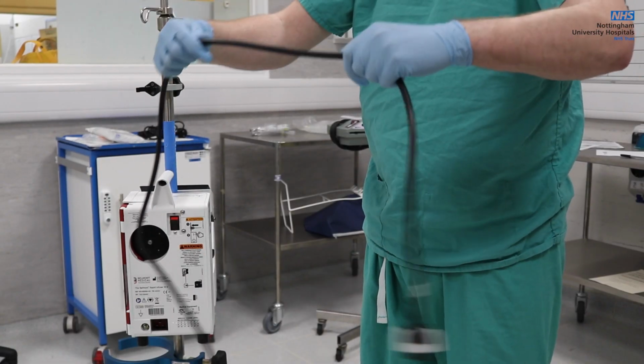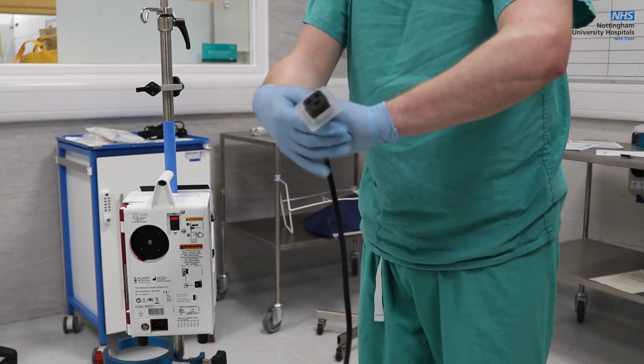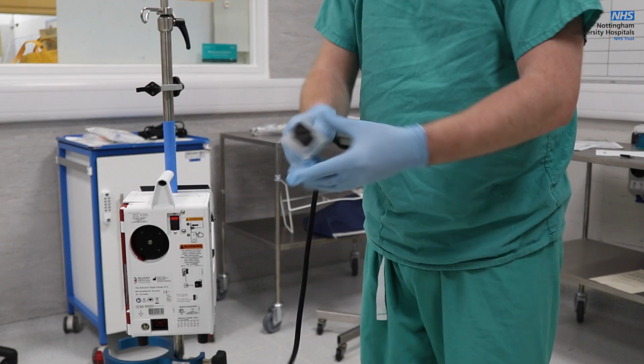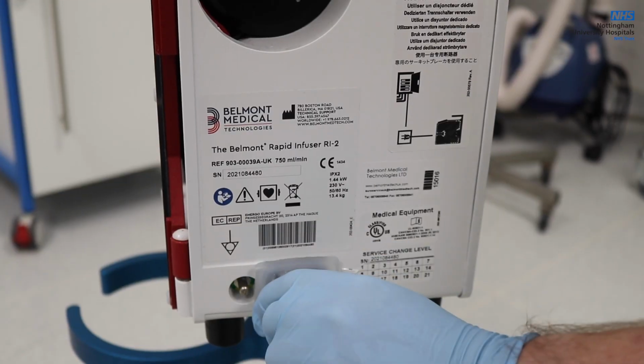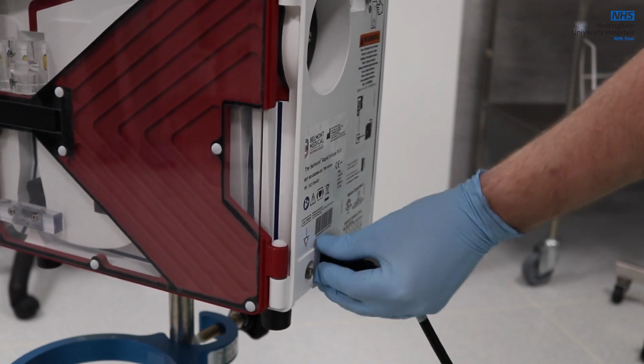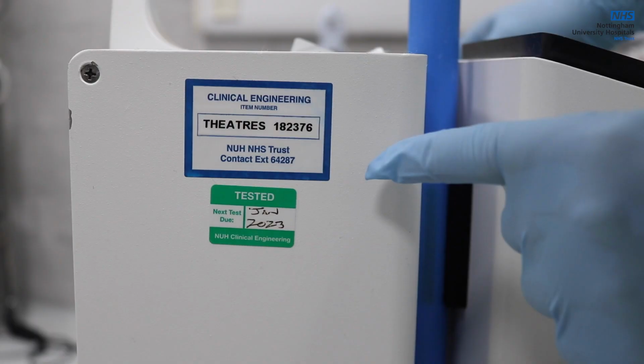Check the mains cable for obvious signs of damage. Check silicone cover and mains input socket is securely fitted. Check fan inlet filters on bottom of the device are free from dust buildup. Check MESU service sticker is on the device and do not use if out of service date. The device is serviced at 6 monthly intervals.